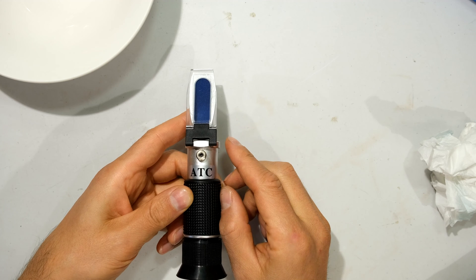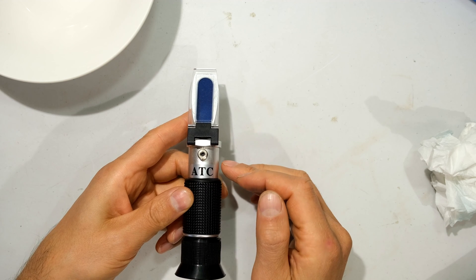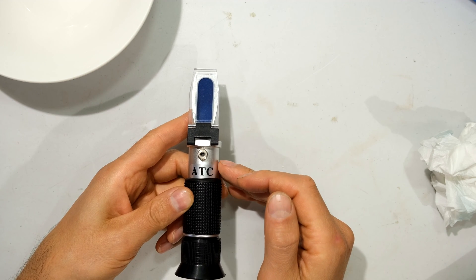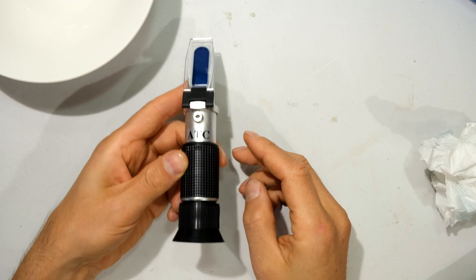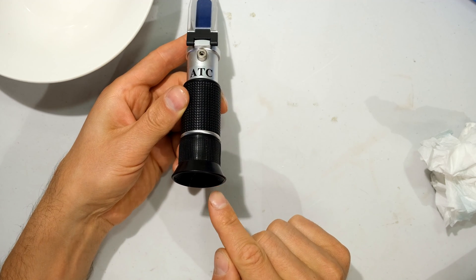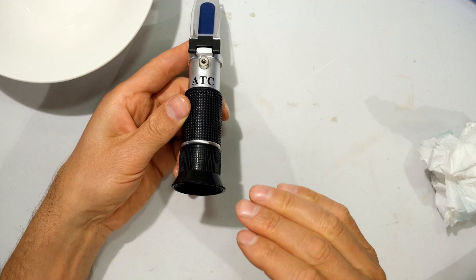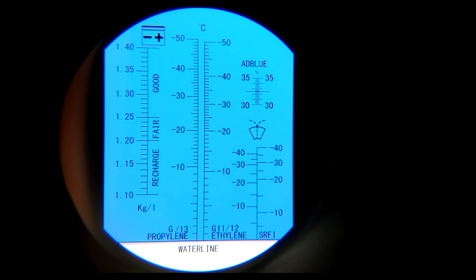In this case, I'm well within that range. I'm at 20 degrees centigrade. Now what you need to do is look in the viewfinder and see if the blue shading is at the bottom line. In this case, you can see that the blue line is exactly on the line that says water line. So in this case, it is calibrated.